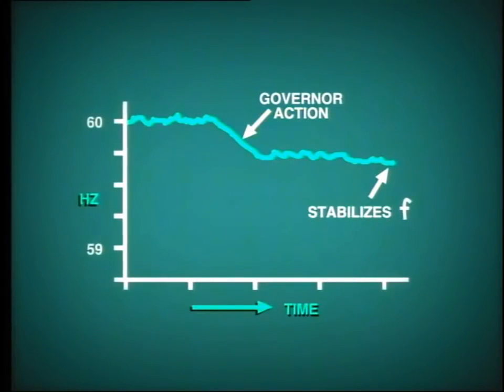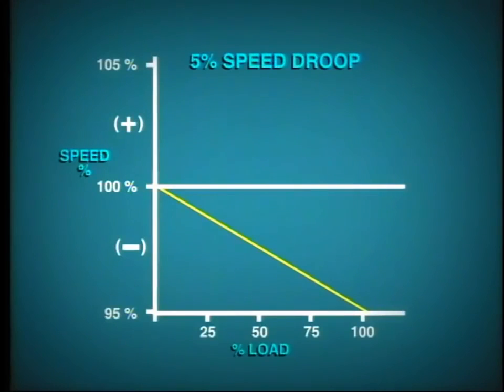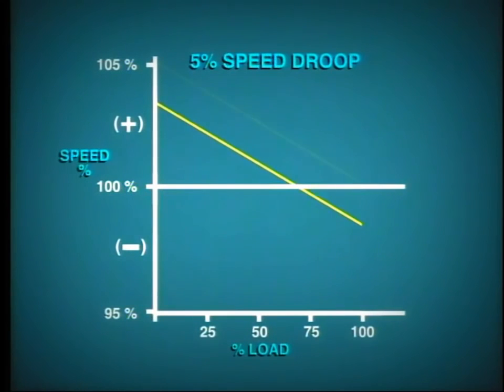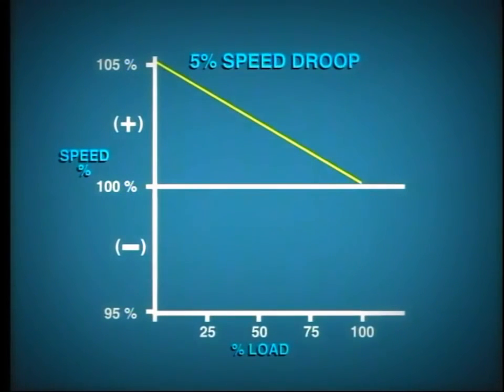However, it is important to note that although each governor moves to stabilize the frequency, it does not return the frequency to its original position. This is due to the regulating characteristic which is built into the governor, known as speed droop. Typically, the turbine governor is set to regulate at 5% speed droop as applied load increases from 0% to 100% power output. Of course, this situation can be corrected easily by adjusting the set point of the governor, which can be done by the operator at various intervals or by automatic frequency control devices.